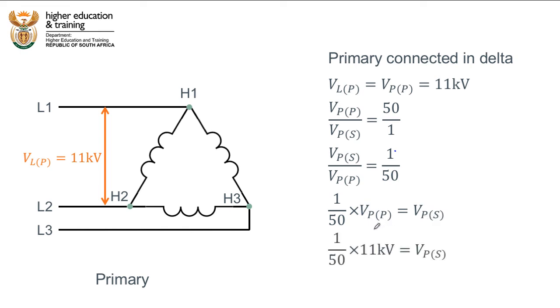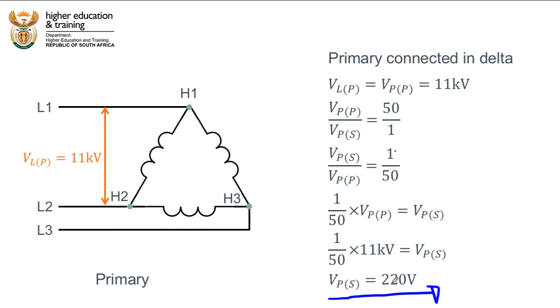I know the primary phase voltage is 11 kilovolts, so I can solve this equation. The phase voltage on the secondary side equals 11,000 divided by 50, which equals 220 volts. That is the single phase voltage that will be supplied to customers.